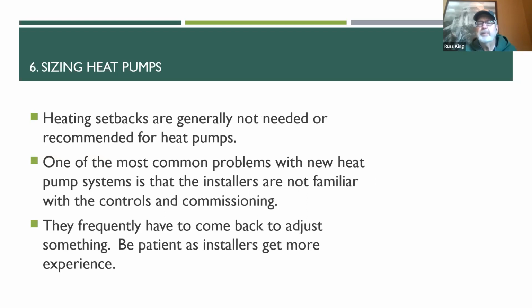And then a lot of times, a lot of utilities will recommend that you have setups and setback temperatures for your air conditioner and heater. It turns out that that's not the best idea for heat pumps. You really want to set it at a constant temperature and just let it run. You can bump it up a little bit, bump it down a little bit, but don't set it back 5 or 6 degrees at night and then it has to recover in the morning.